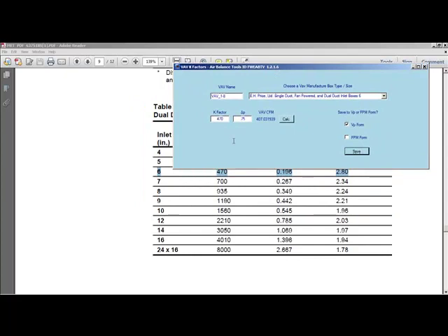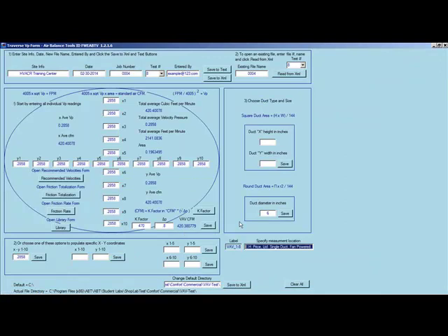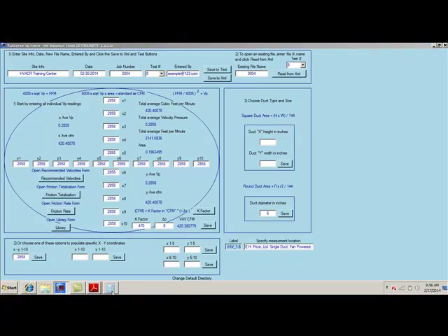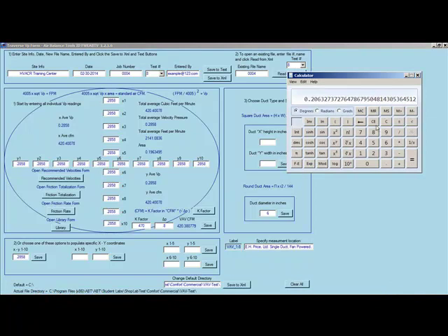It's a K factor of 470, differential pressure of .75. This box would actually be producing 407 CFM. Now we're going to go ahead and go to the traverse. We'll pull up our calculator.